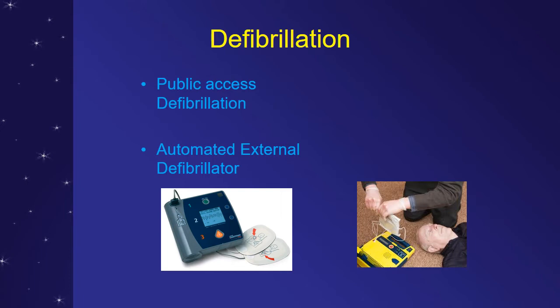So then the machine will detect what this is, because it is sensing through the pads what the cardiac rhythm is, and would say, for instance, okay, so this is a shockable rhythm, please stand away, I'm charging the defibrillator now and will be delivering in a few seconds. And then in a few seconds it will say, okay, I'm delivering energy, do not touch the patient, stand away. So then the resuscitators should stand away without touching the victim.